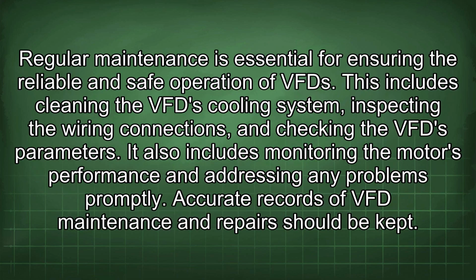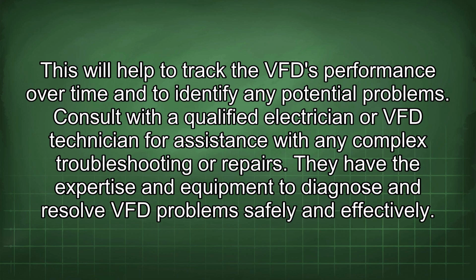Regular maintenance is essential for ensuring the reliable and safe operation of VFD. This includes cleaning the VFD cooling system, inspecting the wiring connections, and checking the VFD parameters. It also includes monitoring the motor's performance and addressing any problems promptly. Accurate records of VFD maintenance and repairs should be kept. This will help to track the VFD performance over time and to identify any potential problems.